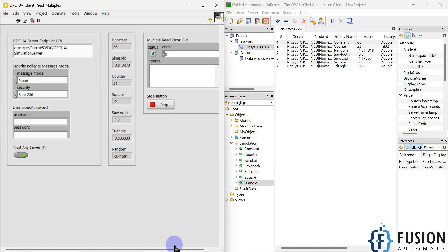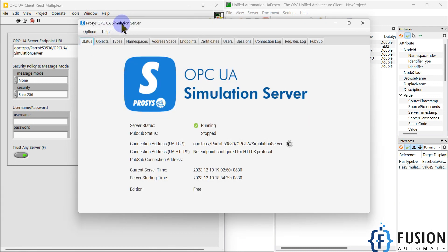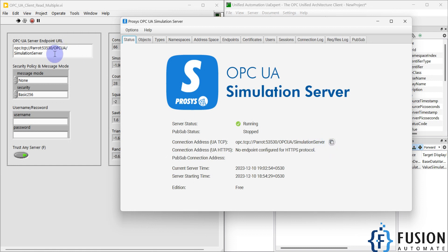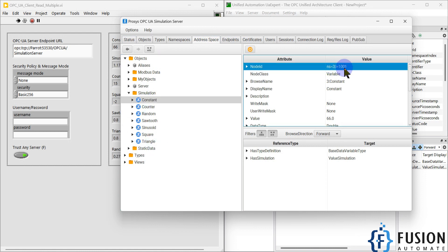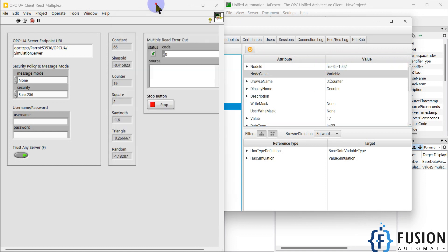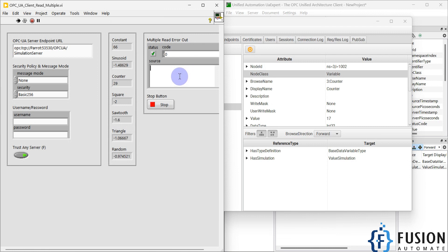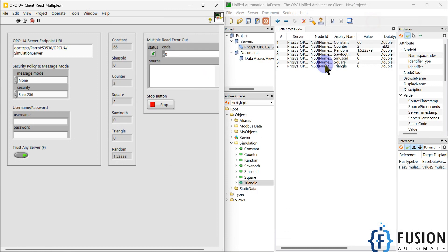We are reading the same tags as in UA Expert. This is the Prosys OPC UA Simulation Server — we used the endpoint URL in LabVIEW, set the message mode and security policy, and did not provide a username and password because none are set for this simulation server. In the address space, each tag has a namespace and node ID, which we used in the backend LabVIEW programming to read the data. If the server is turned off, you will see an error in LabVIEW.